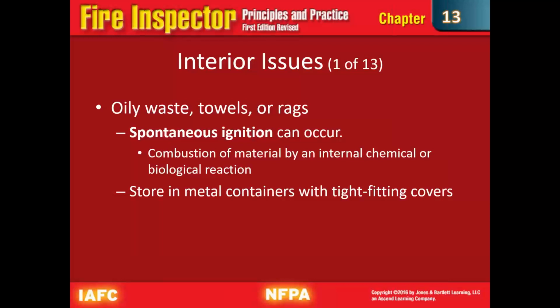For the interior, we look for things that can cause fire, oily rags and things like that, for spontaneous combustion. I've had a couple of cases of spontaneous combustion or spontaneous ignition, as they have it listed as causes of fires. If it is a mechanic shop that has oily rags and stuff like that, make sure that they're stored in a metal container with tight fitting covers, and that's typically to prevent them from catching fire, or the fire from being able to spread.